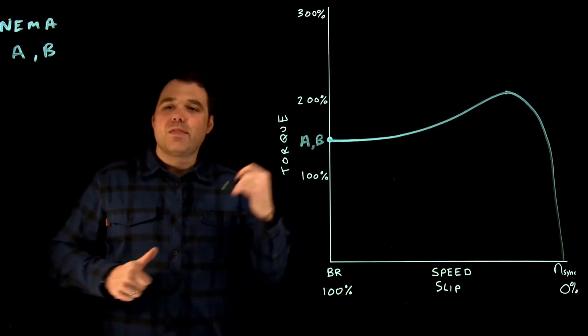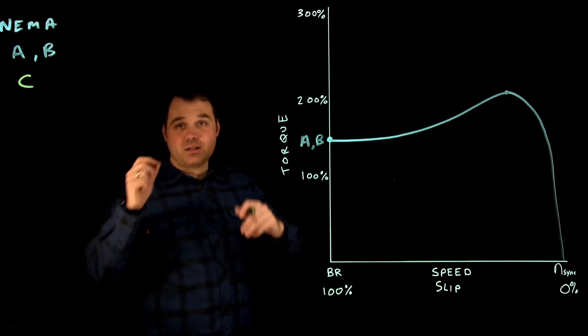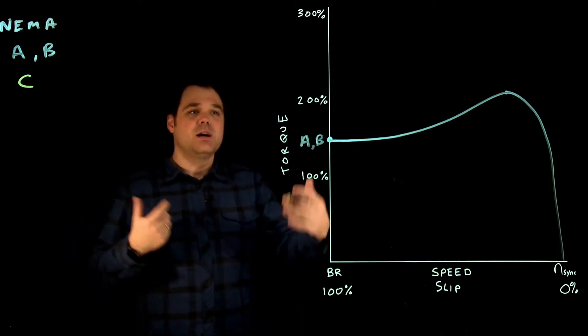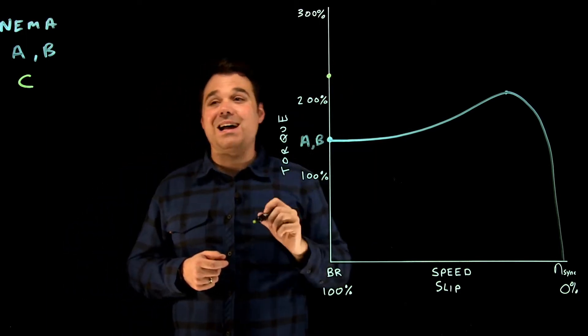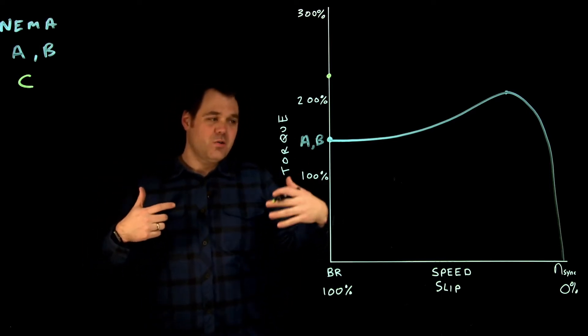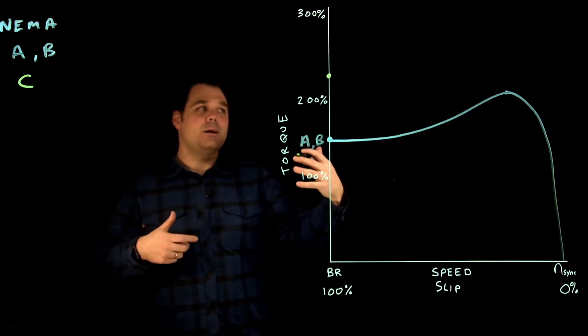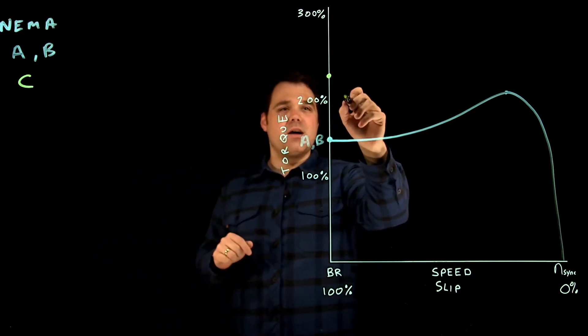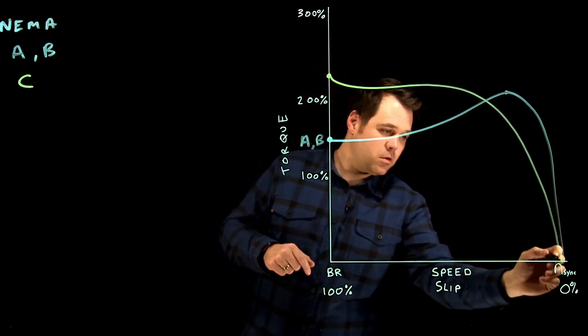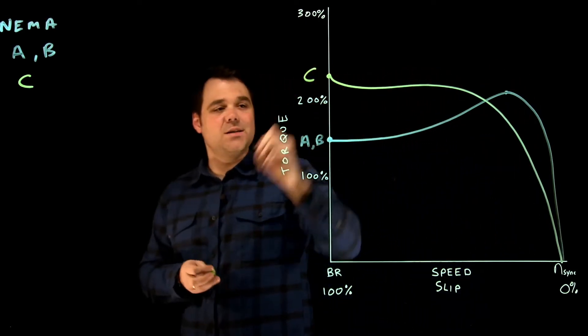Then we come into the NEMA design C. We like the C. The C is that double squirrel cage rotor, so it gives us a more effective start. We get around 225% at start, and that's also where our breakdown torque occurs. Now this motor is a little bit less efficient because of that dual rotor squirrel cage. The torque curve for that one looks like this. The more vertical we are here, the more efficient that motor would be. So that's a NEMA C.